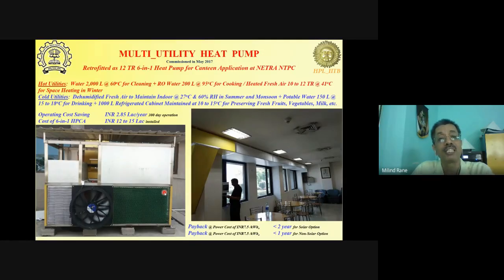Now coming to the next, this is a multi-utility heat pump. It was commissioned in May 2017, and I believe it is still operating well in NTPC Netra. And this is a 6-in-1 heat pump, so 6 different utilities are being catered to using a single unit. This unit looks like this, and it is placed outside the canteen area. This is one third of the space that we are air conditioning. This is the canteen in the NTPC Netra.